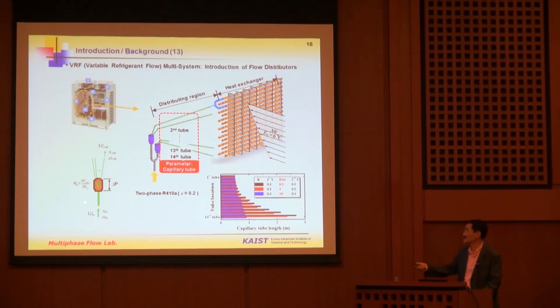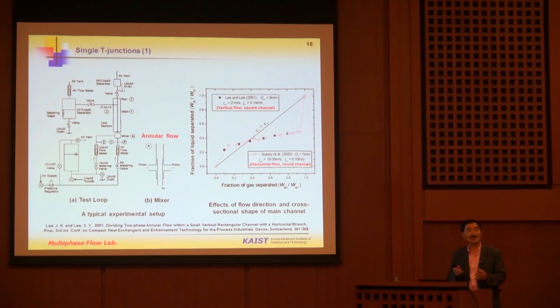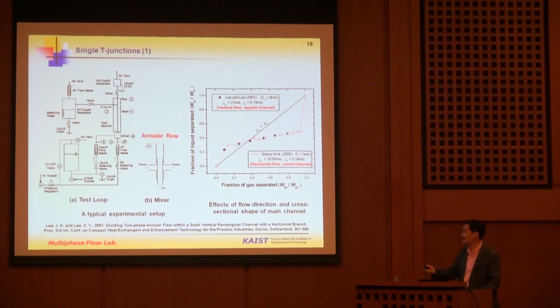Let's start with the single T-junction case. In evaporators and many heat exchangers, even with low quality at the inlet, the flow has very high void fraction. That means the flow pattern easily becomes annular flow or annular mist flow. This is a typical experimental setup: liquid is supplied from one side and air or vapor from another, annular flow is formed, and then flows through the test section through the main.